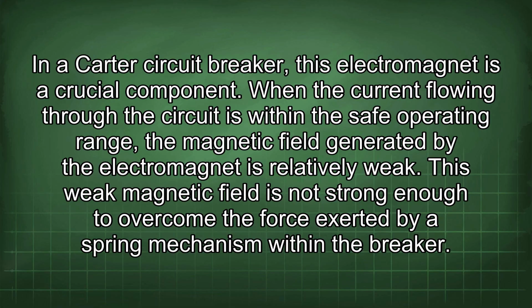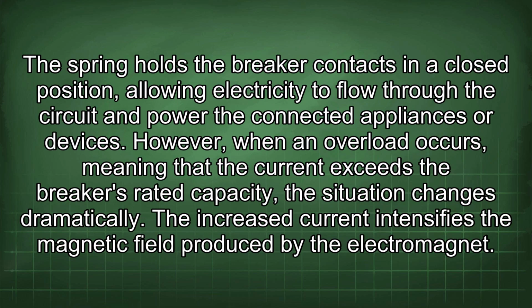is relatively weak. This weak magnetic field is not strong enough to overcome the force exerted by a spring mechanism within the breaker. The spring holds the breaker contacts in a closed position, allowing electricity to flow through the circuit and power the connected appliances or devices. However, when an overload occurs, meaning that the current exceeds the breaker's rated capacity, the situation changes dramatically.